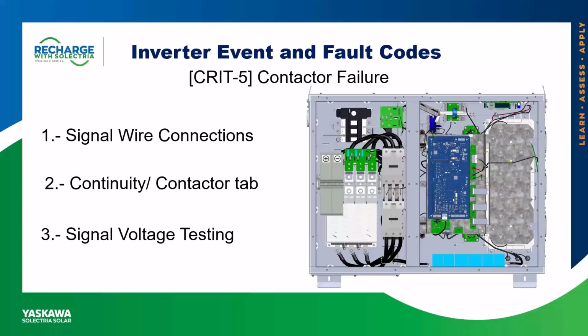So if it's finished the power cycle, you can test to see if there is signal voltage present. If there is signal voltage present and the contactor tab is not pulling in, you know it's going to be definitely a bad contactor. If there is no signal voltage present, then that may be related to a wire harness issue or the digital signal processing board has failed.